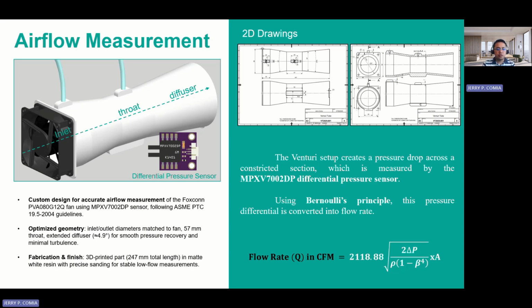To ensure accurate measurements, I've optimized the tube's design. The inlet and outlet diameters match the fan's dimension, and the throat diameter is set to 57 mm. I also incorporated an extended diffuser with a gentle 4.9 degree angle, which helps recover pressure and reduces turbulence. This is especially important when measuring low airflow rates.